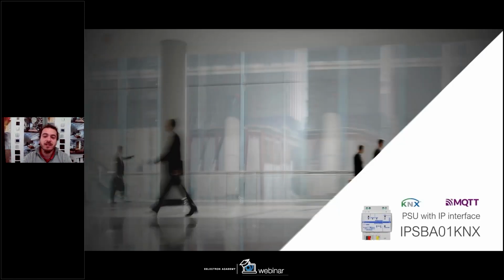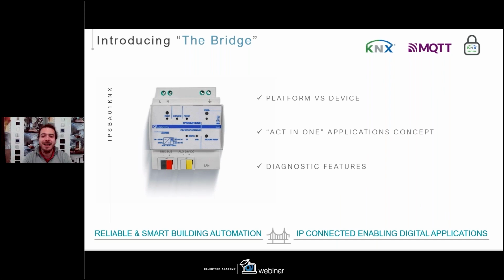The last product that we will see today is the bridge, which is a power supply with IP interface, and the order code is IPS BA01 KNX. The bridge: KNX power supply plus IP connection. So it's like having a power supply plus an IP interface. Pay attention, it's not an IP router. It means that there is no multicast connection and there is no KNX backbone, but we will have a lot of advanced functions that we can enable inside the device, starting from the diagnostic feature, MQTT, schedulers, and others that we will see now.